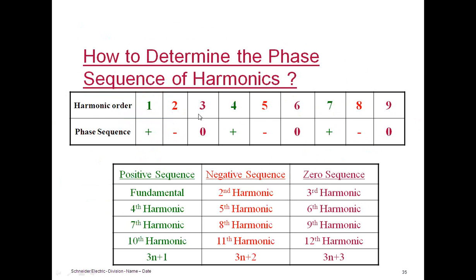harmonic number 3, frequency 150 Hz in a 50 Hz system, and multiples of 3 are zero sequence in nature. That means 3, 6, 9, 12, 15, etc. Any harmonic that is a multiple of 3 is called zero sequence in nature. Fifth harmonic is minus sequence. In many industries we see fifth harmonic more. So we want to understand how this sequence will influence the performance of induction motors, generators, and so on and so forth.